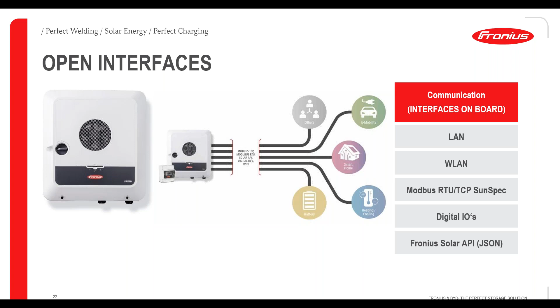The Gen 24 is a very flexible inverter. So we have made some changes to this one from the earlier models. We actually managed to lower the starting DC voltage to 80. And that means that we can basically build a string from 3 panels all the way up to 24 panels. And by having the 80 volt DC, if we have a small area on the roof where we can only fit 3 or 4 panels, we can put it on a string and we have a complete string.